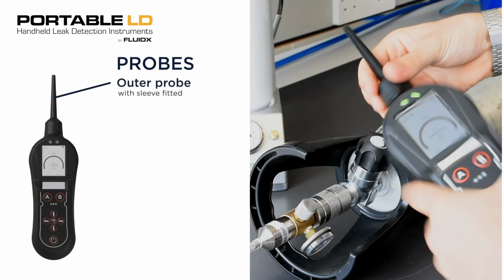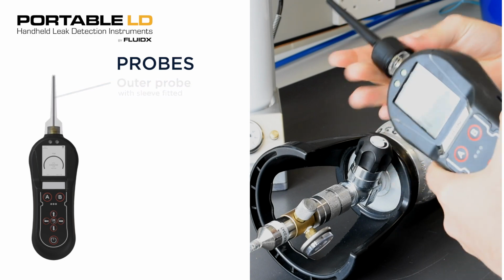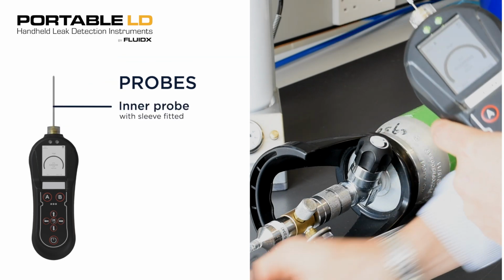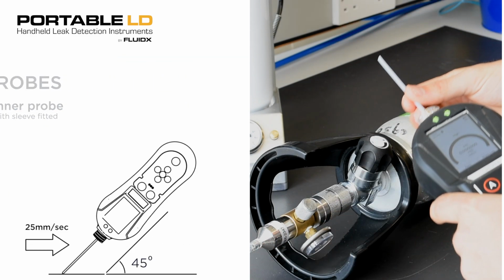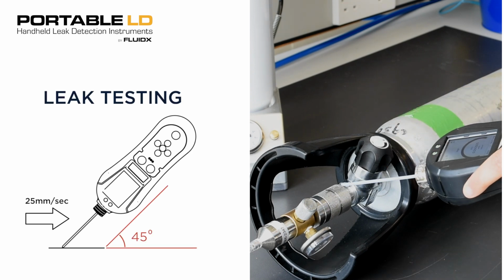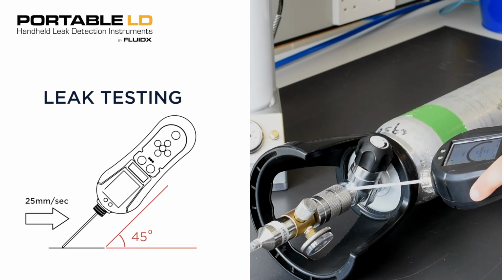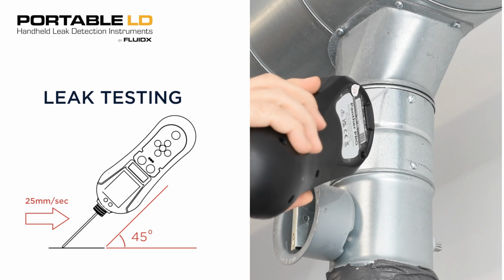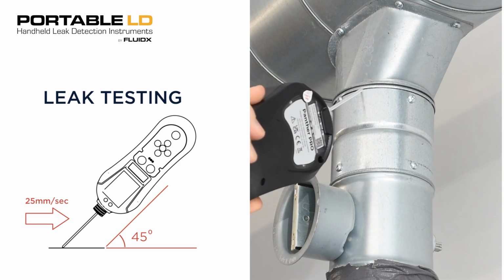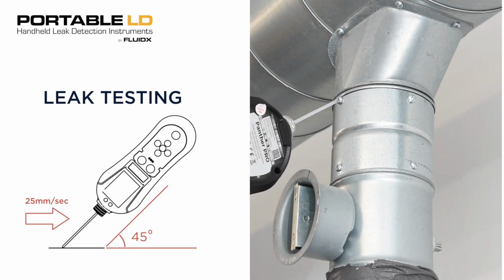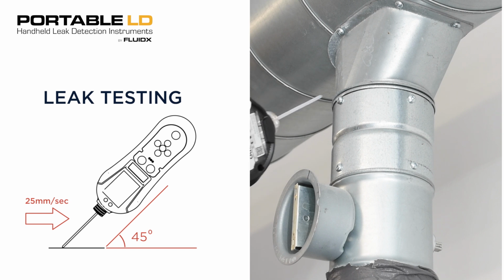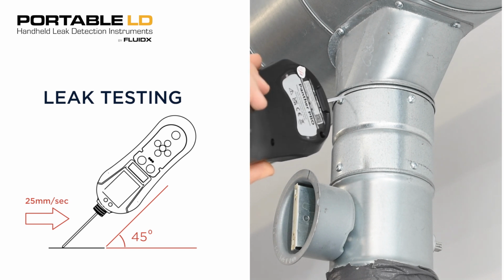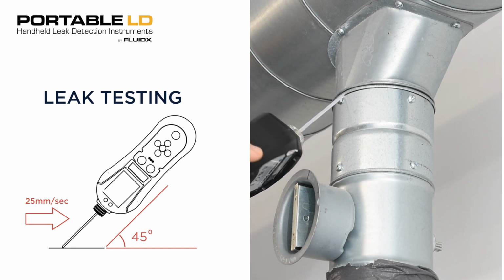The Panther can be used with a protective outer probe attached, but removing it allows the inner probe to reach tighter spaces. Hold the Panther at a 45-degree angle and move the probe along the joint at a rate of about 1 inch per second. If a leak is detected, lift the probe from the surface and go over the area again at a slower speed to pinpoint the leak.